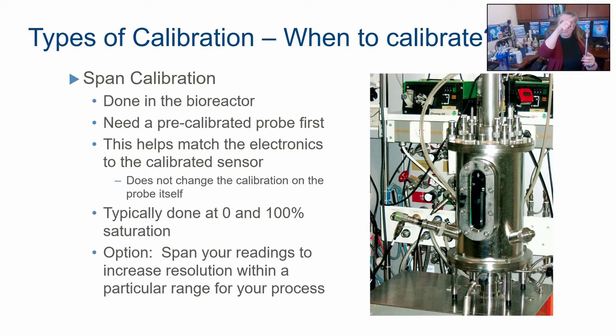And you're going to watch your oxygen signal go down, down, down, down, and then it's going to stabilize. And if it stays stable and it doesn't move and it's at the flat bottom, 5 minutes or so, you're going to say, that's zero. That may take longer or shorter, depending on the media. Your media might be different depending on sugars and salts and all that. But that way, you're always going to the lowest possible signal out reading that's stable for at least 5 minutes in temperature and reading.